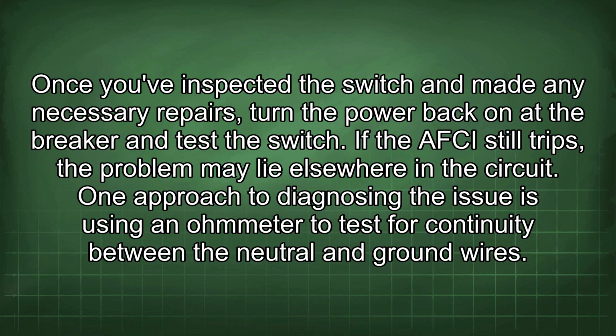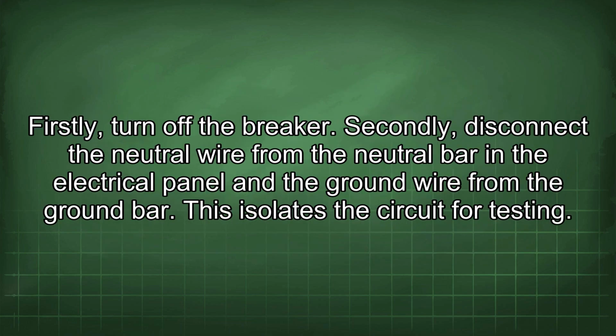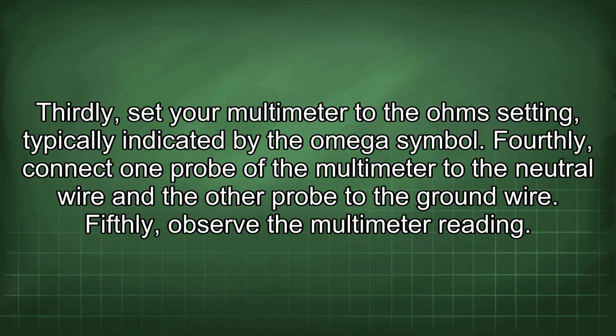One approach to diagnosing the issue is using an ohmmeter to test for continuity between the neutral and ground wires. Firstly, turn off the breaker. Secondly, disconnect the neutral wire from the neutral bar in the electrical panel and the ground wire from the ground bar. This isolates the circuit for testing. Thirdly, set your multimeter to the ohms setting, typically indicated by the omega symbol. Fourthly, connect one probe of the multimeter to the neutral wire and the other probe to the ground wire. Fifthly, observe the multimeter reading.